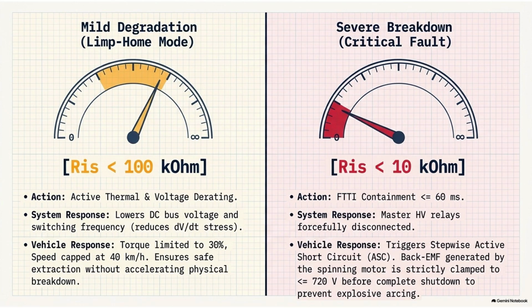It flags that degradation is happening. Yeah. And if it drops below 10K ohms, that is a level 2 fatal fault. That's a very solid way to visualize the baseline health check. But the inherent flaw with pulse injection is that it's periodic. Exactly. A routine checkup is great, but what if a failure happens between those pulses?